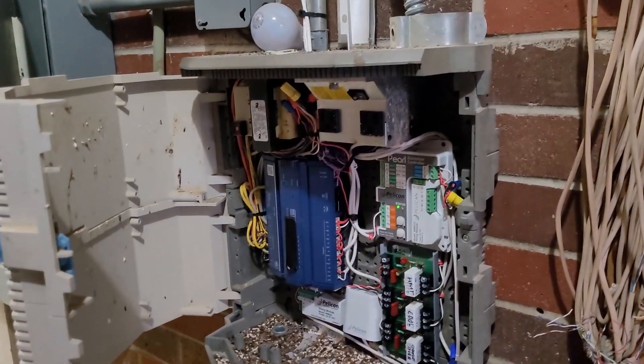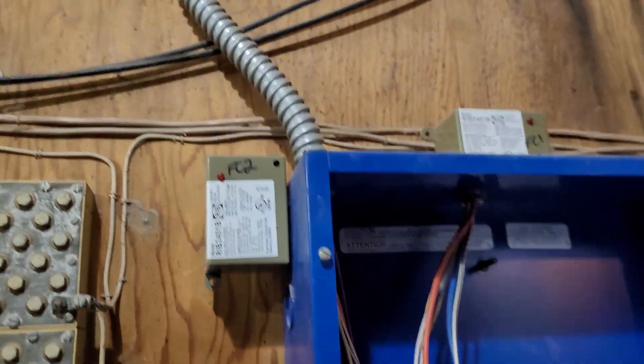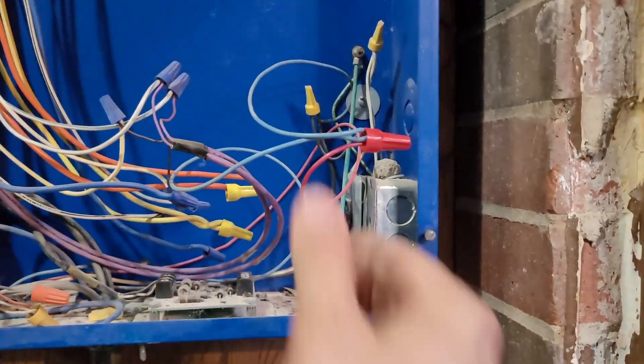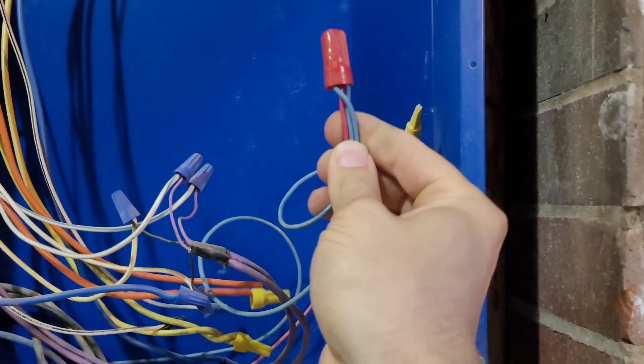They had Metasys in here doing it, and we replaced the Metasys with Distech. The guy didn't realize those relays did anything, so he didn't put them back in — I bet. I've got them all connected, and as I was connecting them — because the wires were live — I heard clicking. They started clicking, so that's good news.